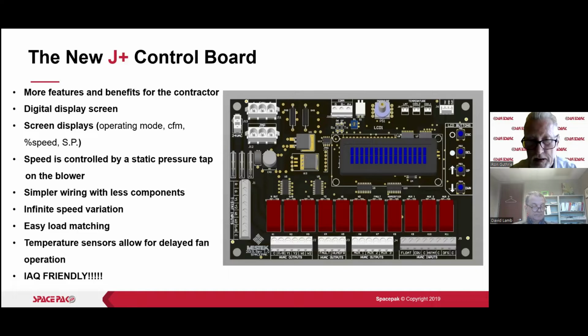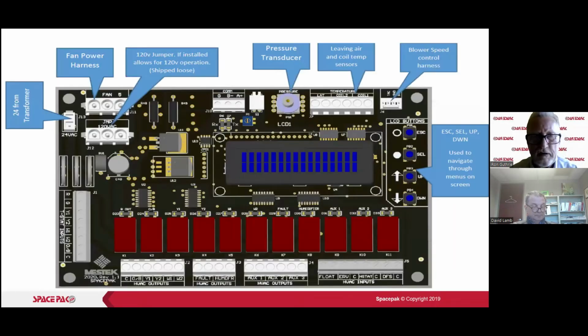So our fan delay on the J series, we had a dial for a fan delay. Always make sure that's set. The systems out there that have problems, the delay's never been set. They've got too much static on the return, and not enough supply air. And we always seem to have all of those things that are wrong with the system when we've got problems with the system. Okay, so we're also IAQ friendly here as well. And we'll talk about those temperature sensors in this frame here.